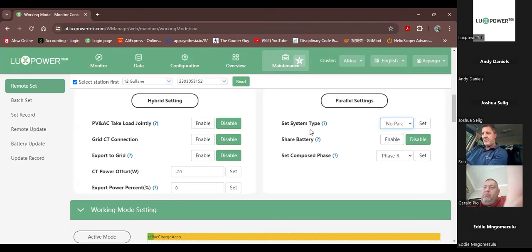You simply look at the diagram: if you've got two machines, then both switches on both machines will be on. If you've got three, then it's the first one on, middle one off, and the last one on, and so on it goes. It'll always be the first and the last in the on position, and the middle machines have to be off. And that works the same for single phase and for three phase parallel.